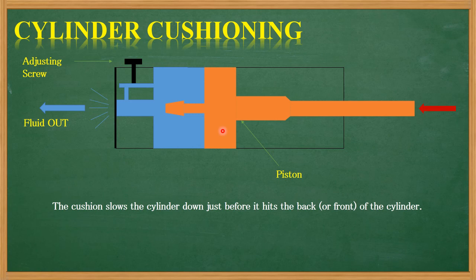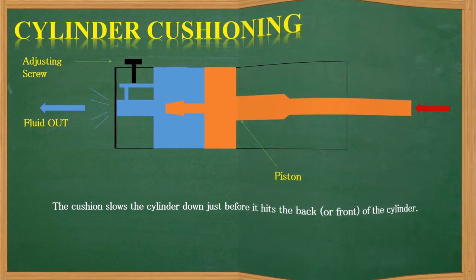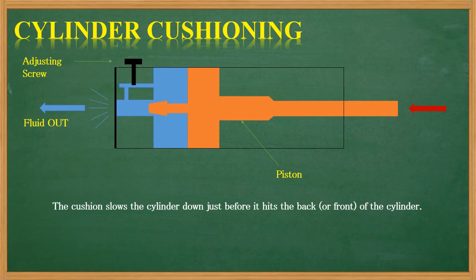Now let's see how cylinder cushioning works. The piston on the right side — when oil comes from that side it moves to the left. As it moves left, oil exits freely from one side. But once that specific cushioning spigot portion enters the bore, fluid faces a restriction in exiting, oil flow reduces, back pressure builds up, and the piston slows down gradually before reaching the cylinder end, preventing impact.